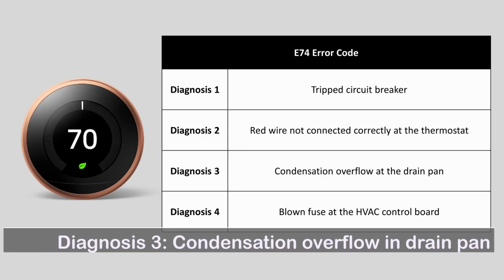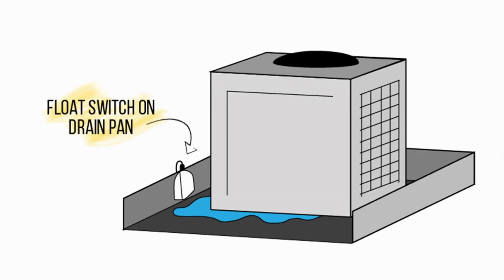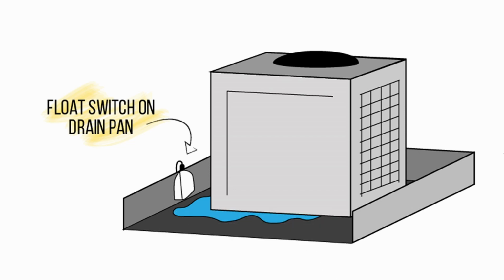Diagnosis 3. Condensation overflow at the drain pan. The drain pan is located at the bottom of the HVAC system. It collects and drains water condensation, so the water won't flood your house. There is a float switch at the drain pan that turns off the power to the system if the water level is too high in the pan.